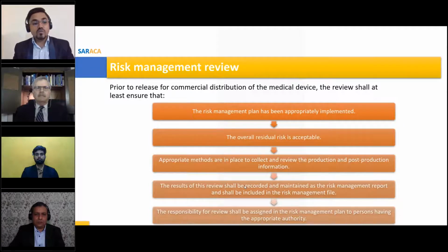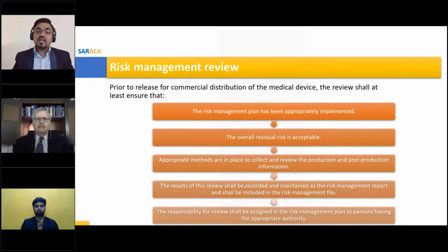If yes, then you go on to the overall residual risks. You need to check the overall residual risks which were estimated or evaluated throughout the risk management activities, and whether those overall residual risks are acceptable or not. If acceptable, you go on to the further process. Then you need to check whether appropriate methods are in place to collect and review production and post-production information.